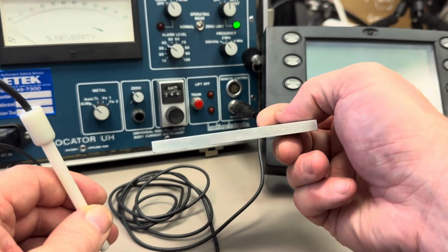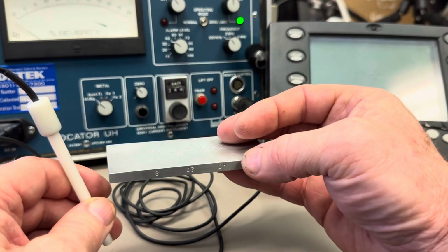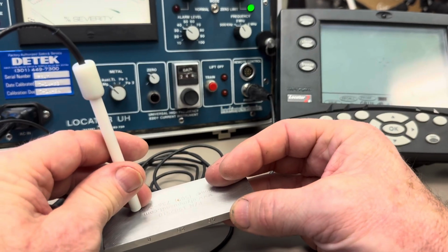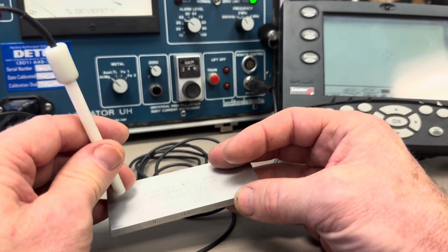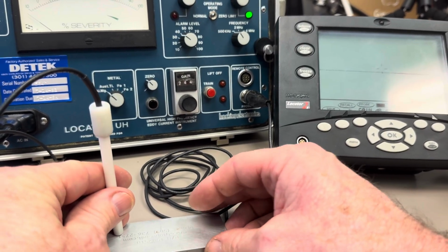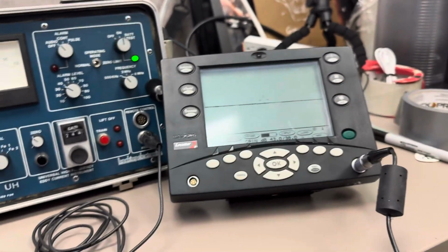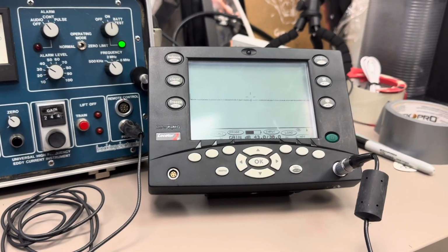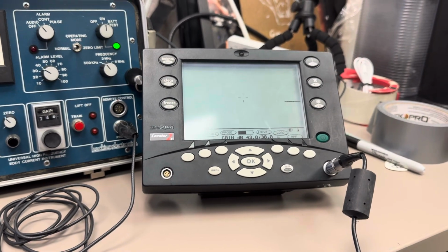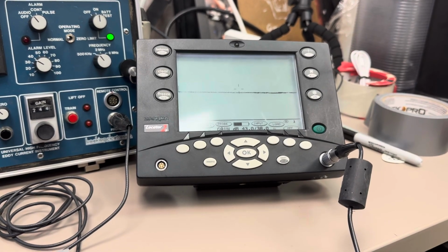But if this was only 1/10 of an inch thick and I turned it over so my cracks were on the bottom side, and then I took a wide enough coil and used low enough of a test frequency, because we need all those things to penetrate some amount. So if I would scan it then and I was seeing a far surface flaw, then our phase would be much over to the right or rotated clockwise, because there's more phase lag with a far surface flaw. So the impedance plane instruments give you a lot of flexibility because you are able to separate the variables based on phase.